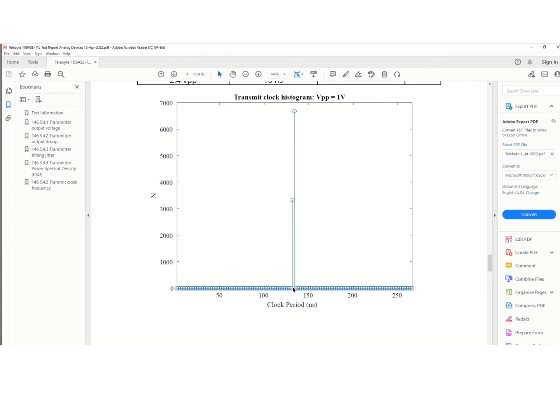Then we get a histogram, the transmit clock histogram. And the period is 133.3 nanoseconds for 10BASE-T1L, and you can see we're measuring 132 and 134 nanoseconds. So we're right in the middle of those two values. And then we have the transmit clock frequency. So we measured 7.499884 megahertz, and we must be between 7.499625 megahertz and 7.500375 megahertz. So that's a pass.